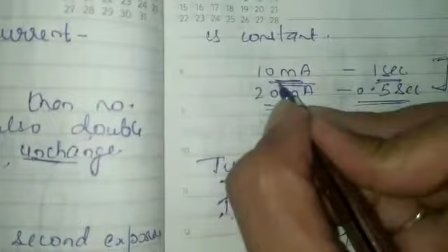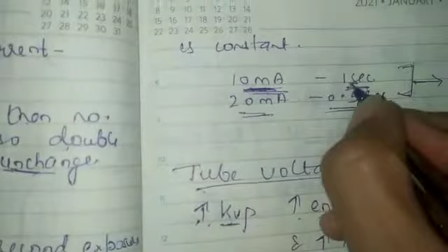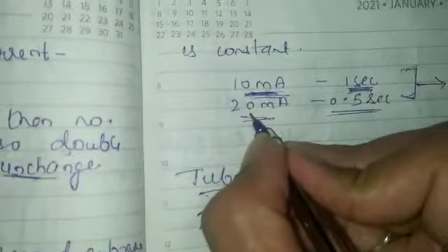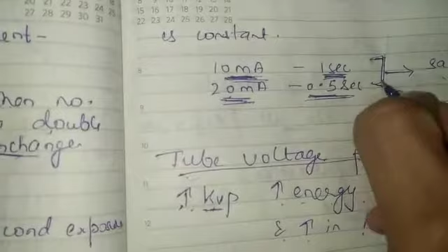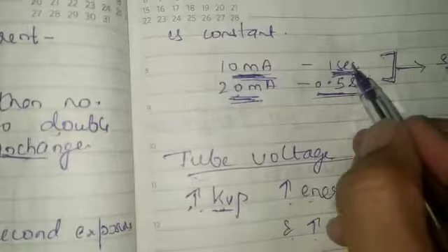Quality will be constant. For example, at 10 mA tube current and 1 second of exposure time, if you increase the tube current to 20 mA and decrease the exposure time to 0.5 second, the quality will be the same. So the quality doesn't depend upon the exposure time and tube current.